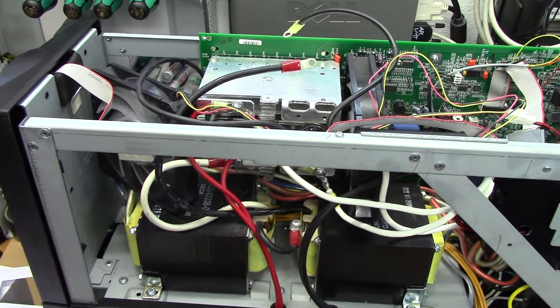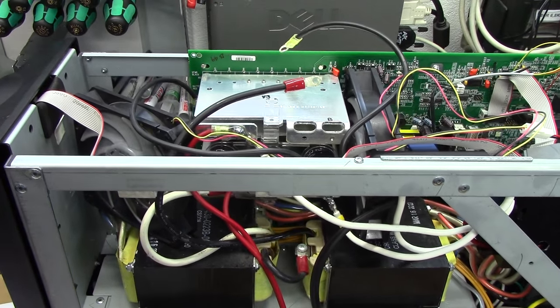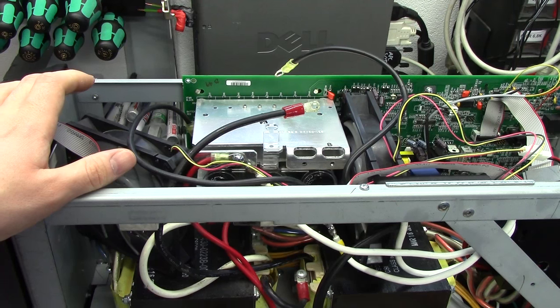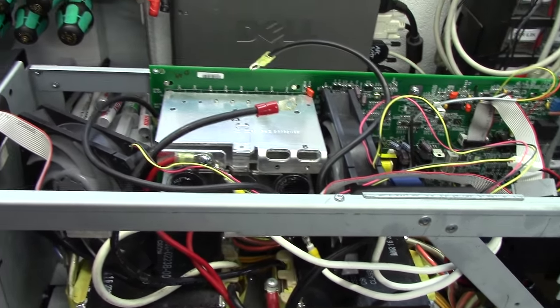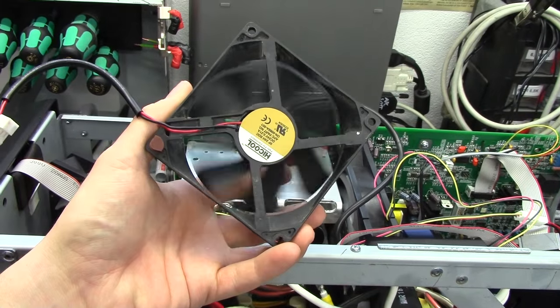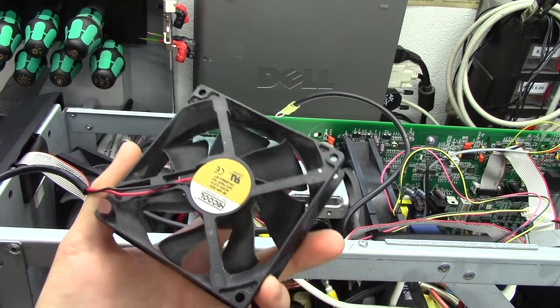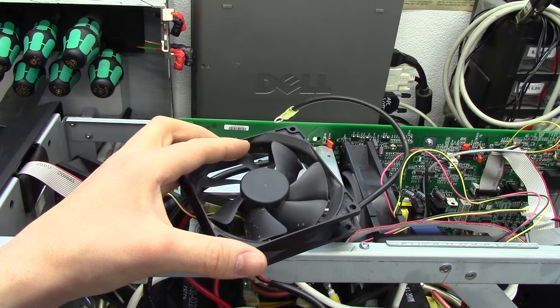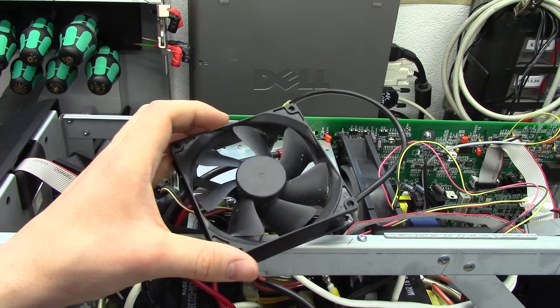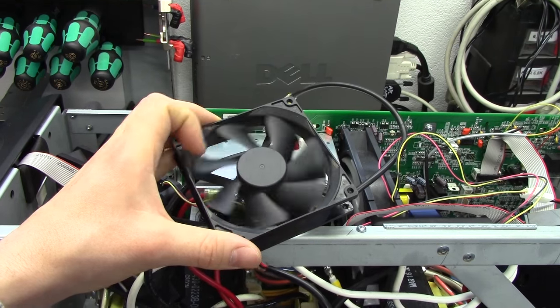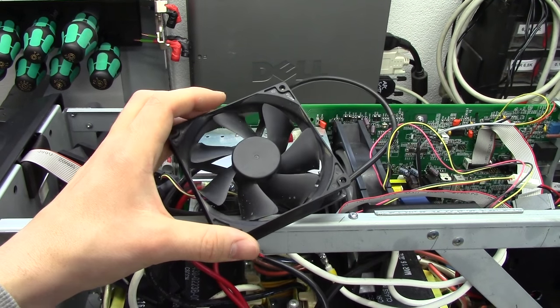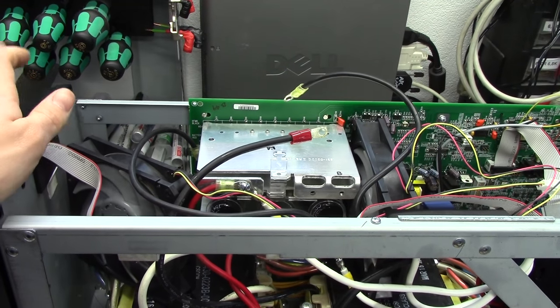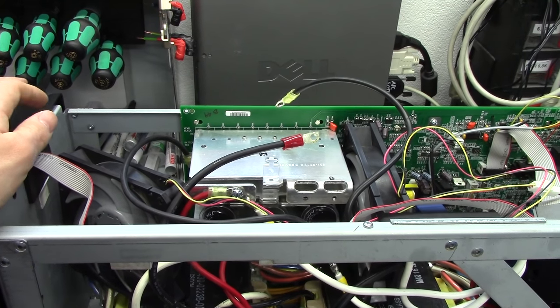Moving on with the SMT2200 project, I'm starting to think a bit about cooling. If I'm to actually get any kind of decent continuous power out of this thing, the original single 92mm fan has definitely got to go. The basic consumption of this unit seems to be about 40 watts when it's in line interactive mode, about 70 watts when it's running as an inverter.